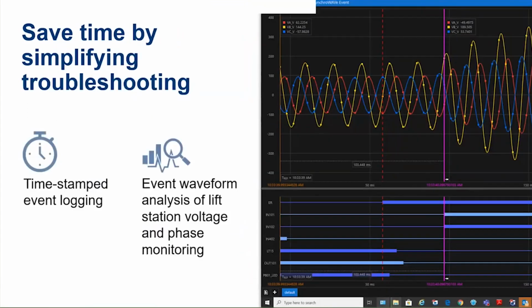So speaking of knowing what happened, this is an event report that we pulled out of a pump controller at a lift station with an open delta connection to their electric utility's power supply. This was when they switched over to generator power, and what you'll see is there's an orange bar on the left, and then there's a purple-pinkish bar on the right, about halfway through the graph.